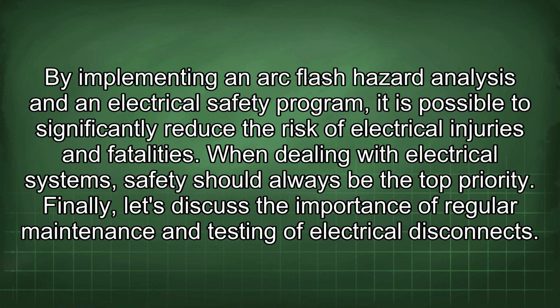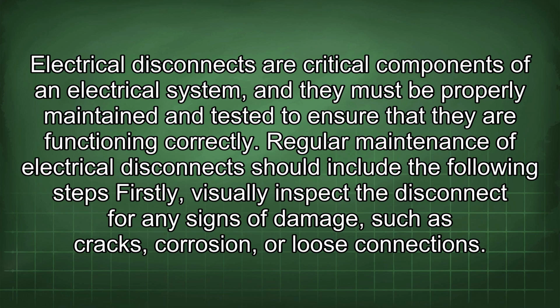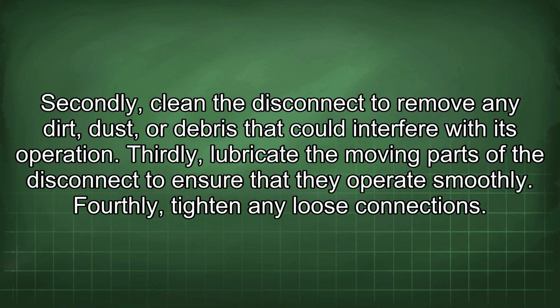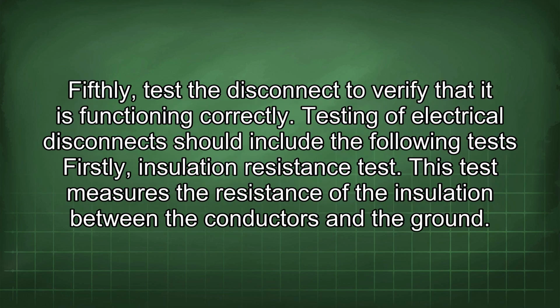Finally, let's discuss the importance of regular maintenance and testing of electrical disconnects. Electrical disconnects are critical components of an electrical system, and they must be properly maintained and tested to ensure that they are functioning correctly. Regular maintenance of an electrical disconnect should include the following steps. Firstly, visually inspect the disconnect for any signs of damage, such as cracks, corrosion, or loose connections. Secondly, clean the disconnect to remove any dirt, dust, or debris that could interfere with its operation. Thirdly, lubricate the moving parts of the disconnect to ensure that they operate smoothly. Fourthly, tighten any loose connections. Fifthly, test the disconnect to verify that it is functioning correctly.